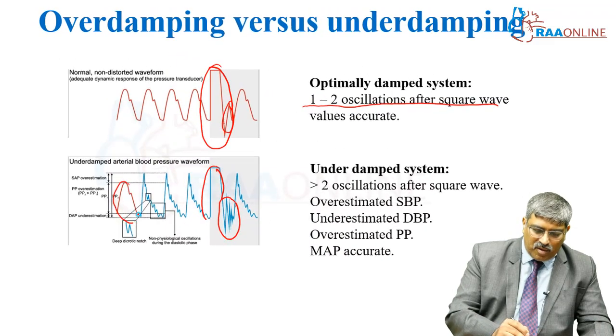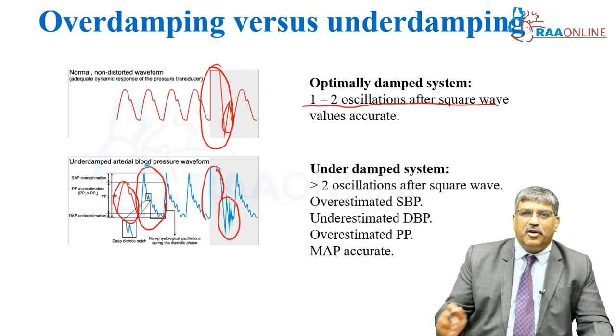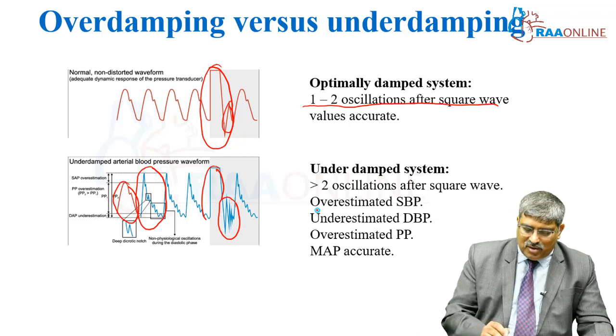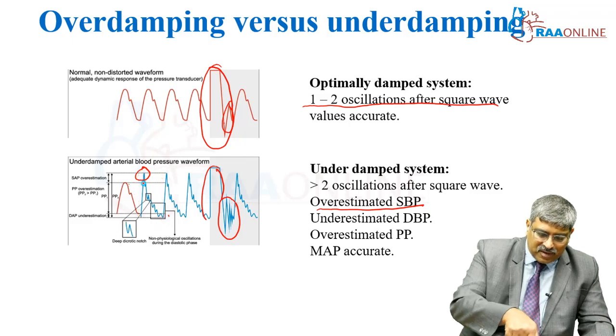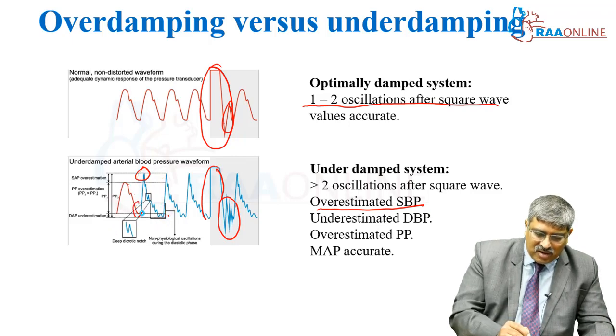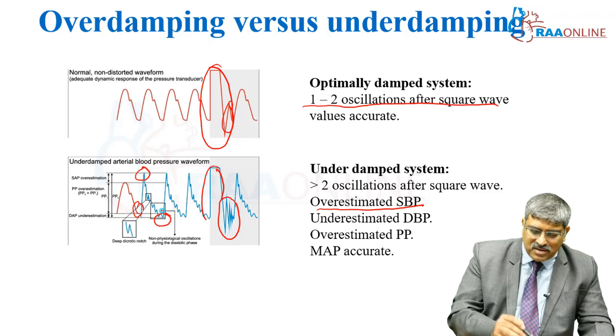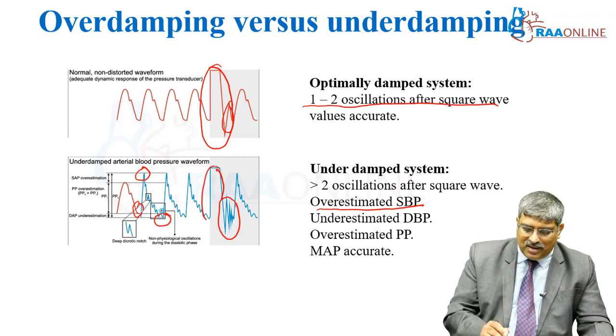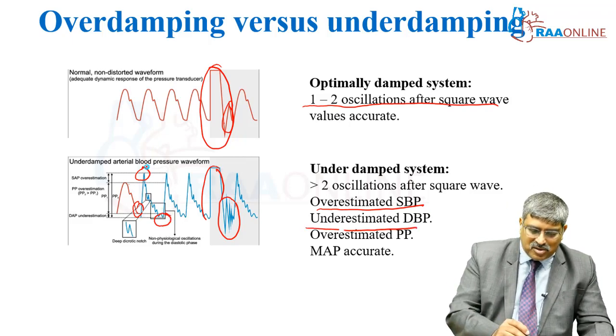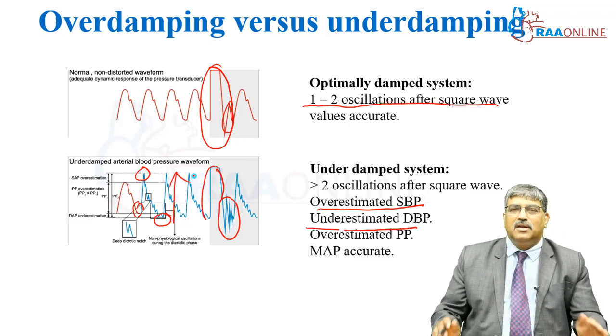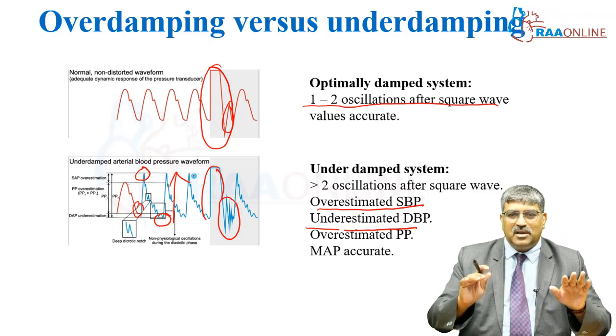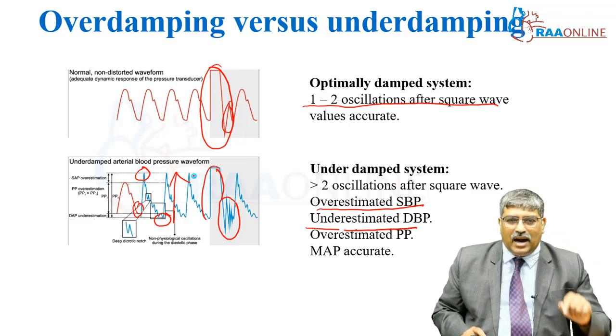Comparing a normal waveform to an under-damped waveform: in under-damping, the systolic blood pressure is overestimated. The diastolic pressure is underestimated because the systolic pressure is elevated. The pulse pressure is also overestimated. However, the mean arterial pressure remains the same. That is under-damping.